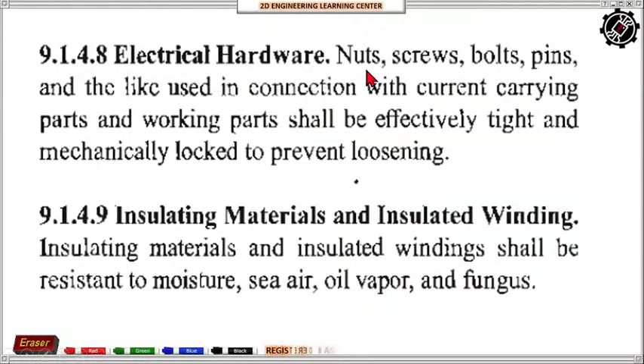Electrical hardware, so nuts, screws, bolts, pins, and the like used in connection with current carrying parts and working parts shall be effectively tight and mechanically locked to prevent loosening. So there must be a proper tightening of all the fasteners, no? Insulating materials and insulated winding. So insulating materials and windings shall be resistant to moisture, sea air, oil vapor, and fungus.